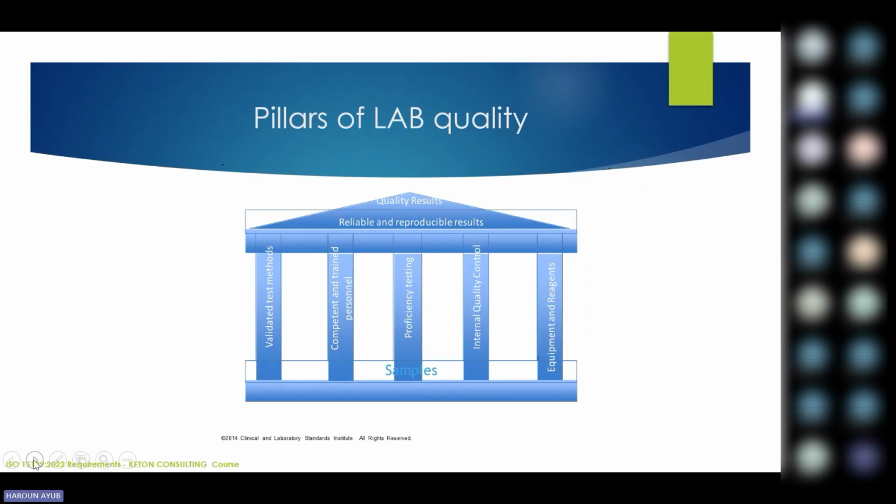Once you employ a new test in your organization, ensure that the process is validated. Once you acquire new equipment, ensure that it's properly validated. And once the equipment manufacturer or the installer has done their installation qualification and operation qualification checks at the lab, you need to follow and confirm the performance qualification checks. In the performance qualification checks, you are checking the claims that the manufacturer has put in place, whether they conform to what the equipment is actually doing.